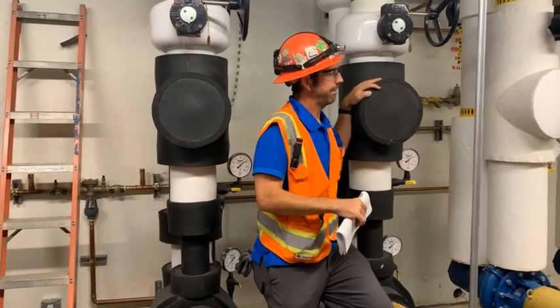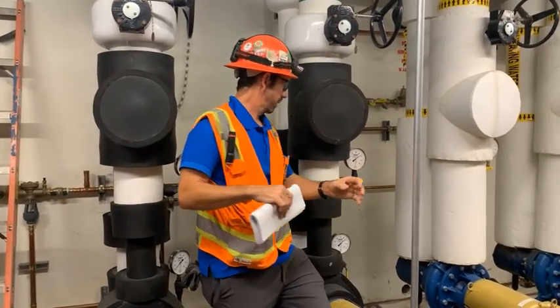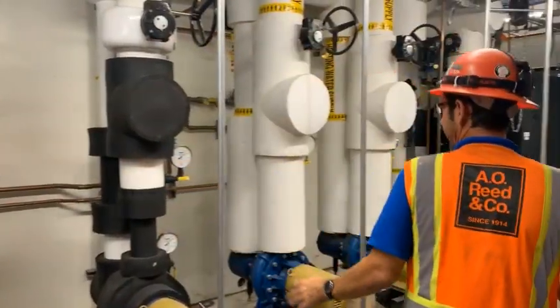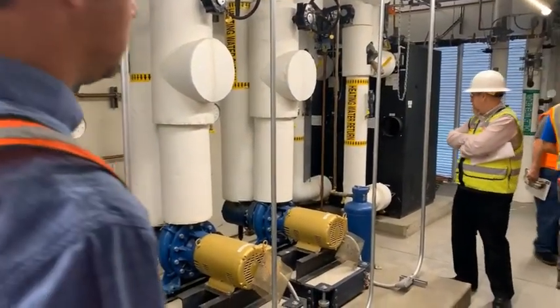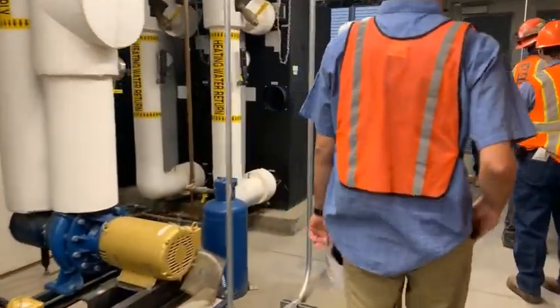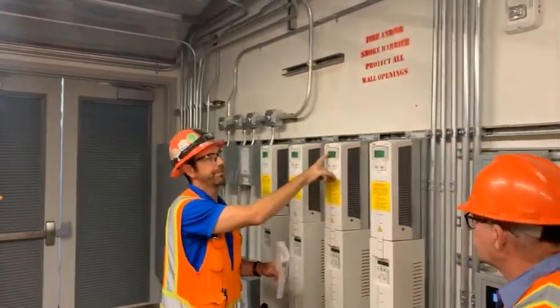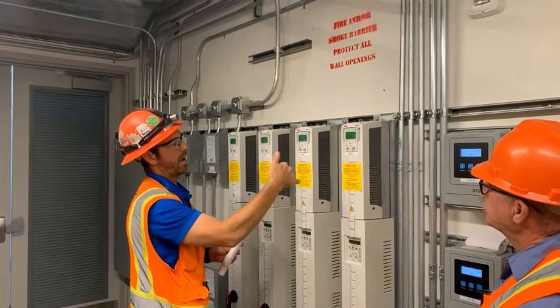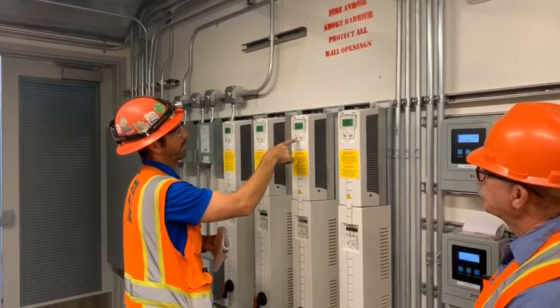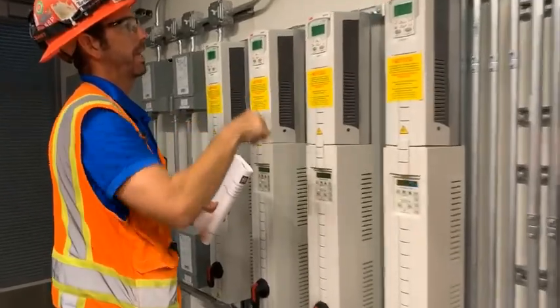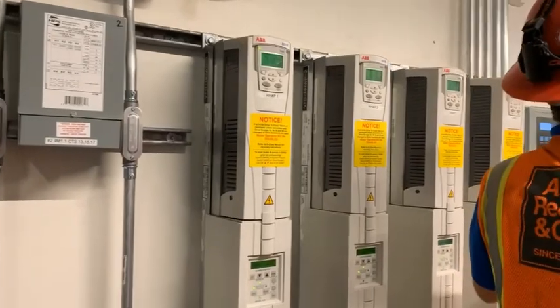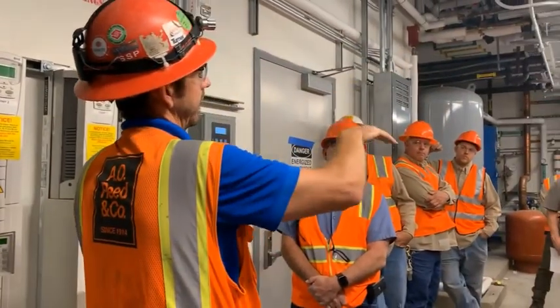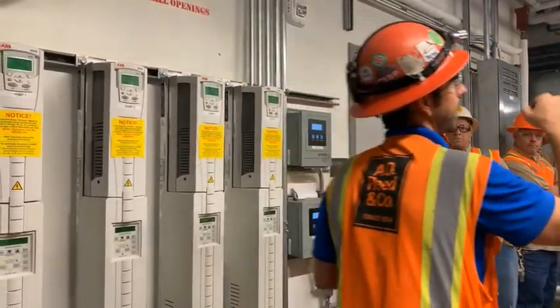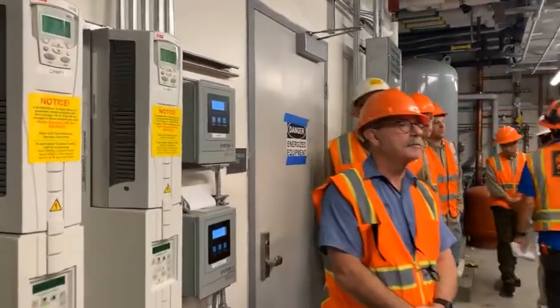So right now we don't have any chilled water pumps running. What we first want to do is look at the front end and see what the differential pressure is. If we're in here, for some reason somebody's turned off this pump. It's in off mode. We'll have VFD training too on a different day. But right now, control is trying to turn this pump on and it's in off mode, it won't run, okay? Part of this is that they might not need to run a pump, okay? If the DP from the plant is high enough, or if the DP in the building is high enough and we don't need to run one of our pumps, there's a bypass loop up here with a check valve. It goes around the pump.